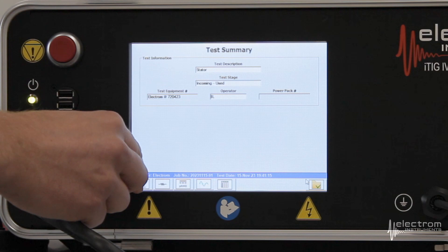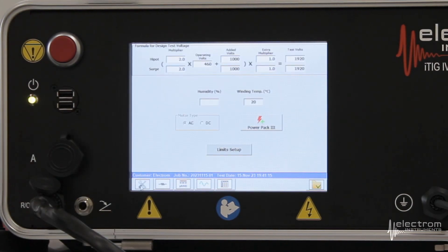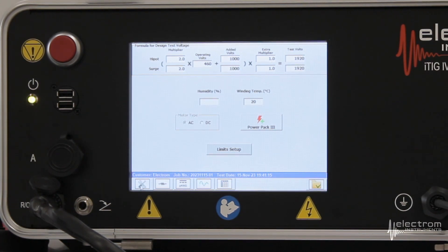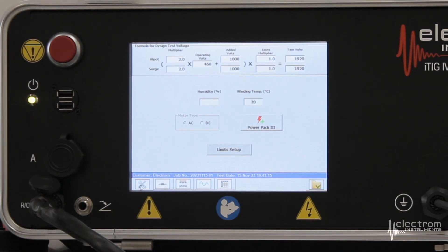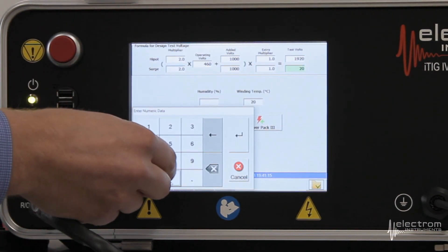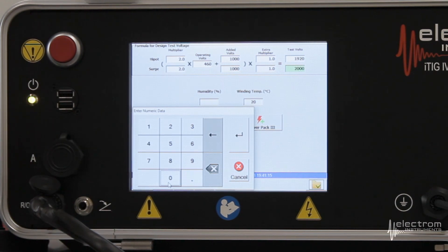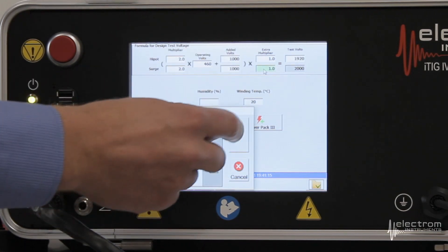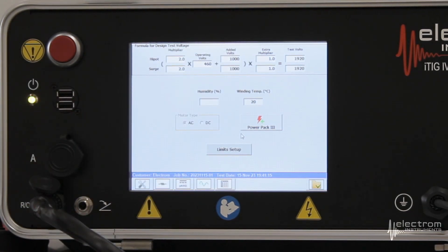Next step is the setup screen. At the top of the screen you see the high pot and surge test voltage formula. The default is two times the operating voltage plus 1000 — in this case that ends up being 1920 volts. If you don't like the formula or the final test voltage, you can click any of the white fields and change it. For example, if we want to do the surge test to 2000 volts, click the field, type in your voltage, and hit Enter. To revert, click the field and hit Enter to default back to the formula.